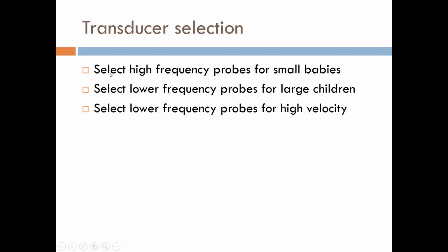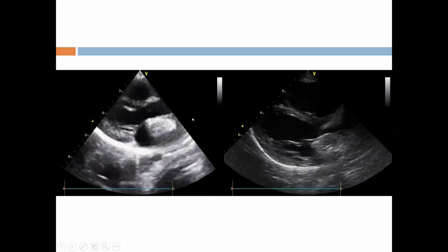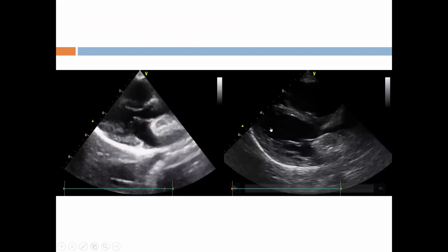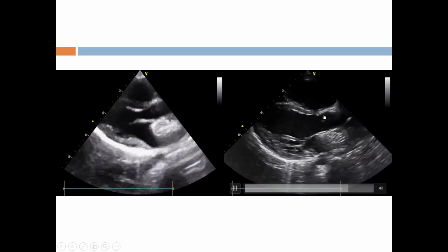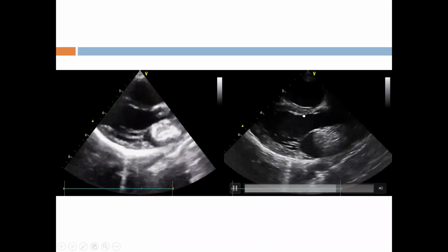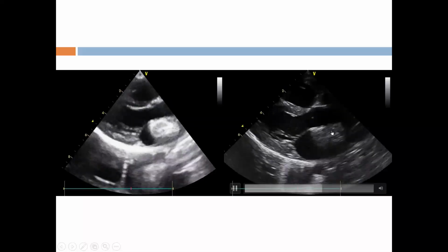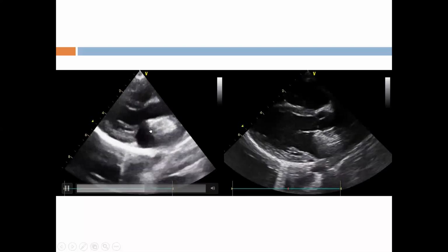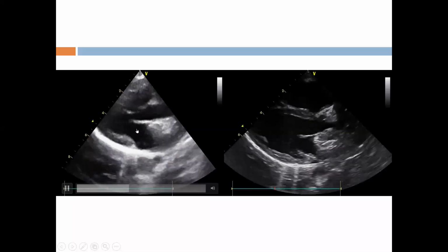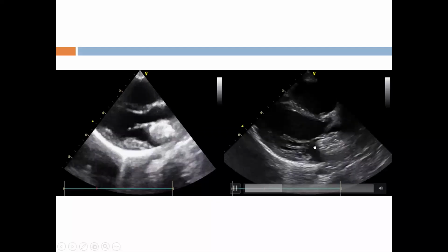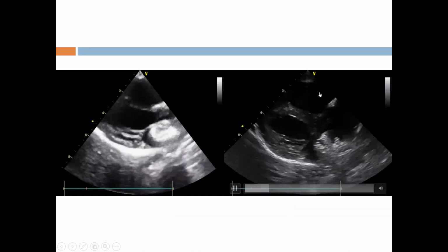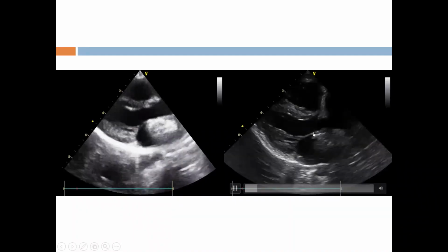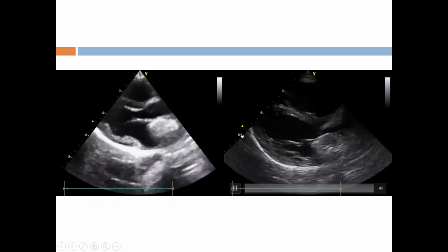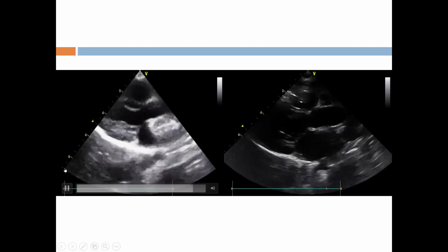Selection of the probe. Select a high frequency probe for small babies and a low frequency probe for the larger babies. For high velocity, select low frequency probes. This is an adult probe and this is a pediatric probe. You can see that the structures are seen very well in the second image, but in the first case the structures are denser and the clarity of the valve is not much. Here, the valve clarity is very good. This is the high frequency probe and has a good resolution. The penetration is poor, up to 6 centimeters, but the penetration over here is up to 15 centimeters.